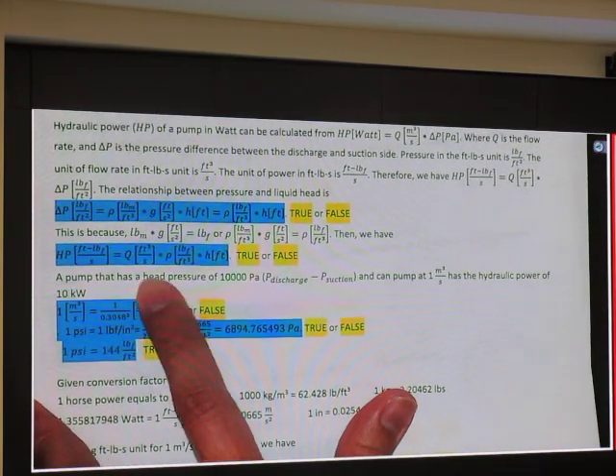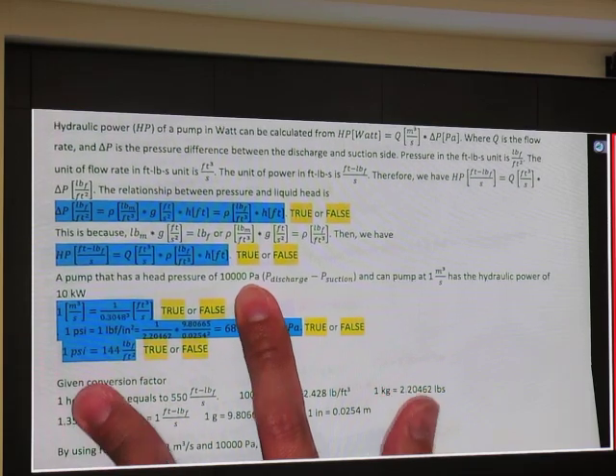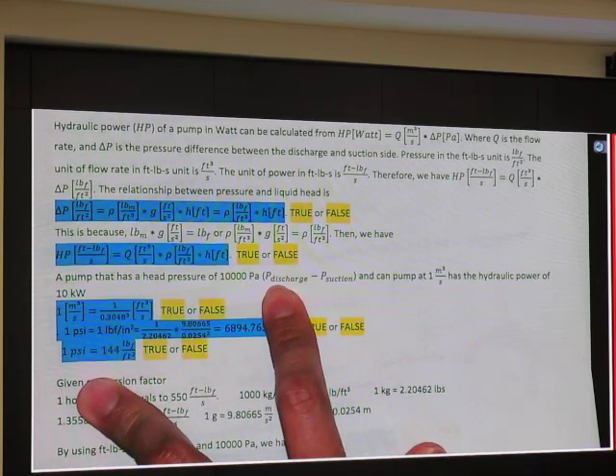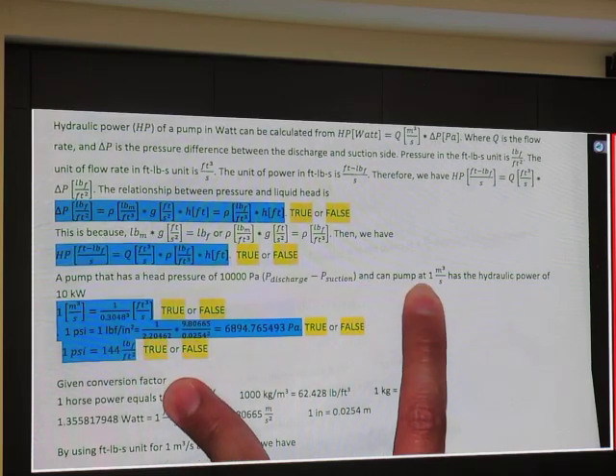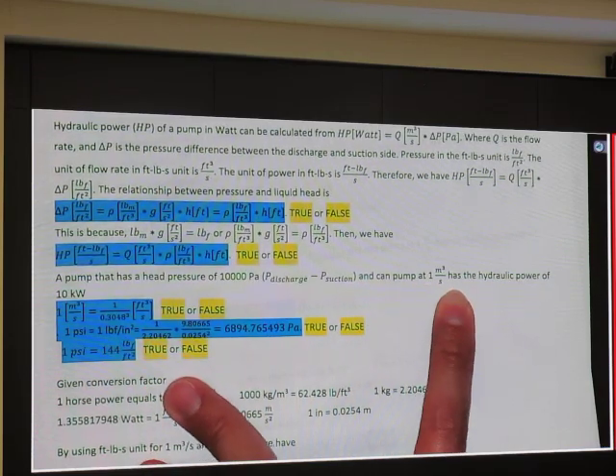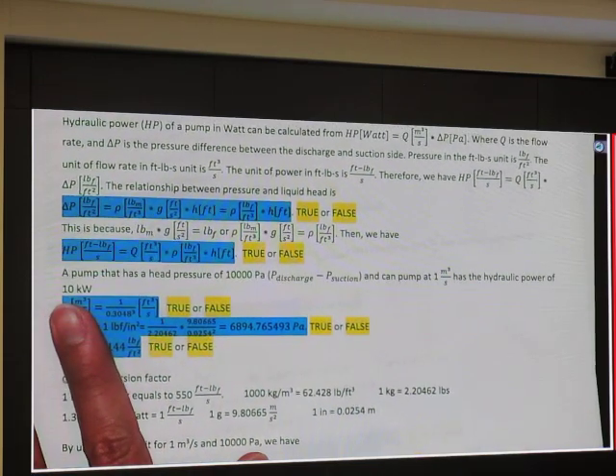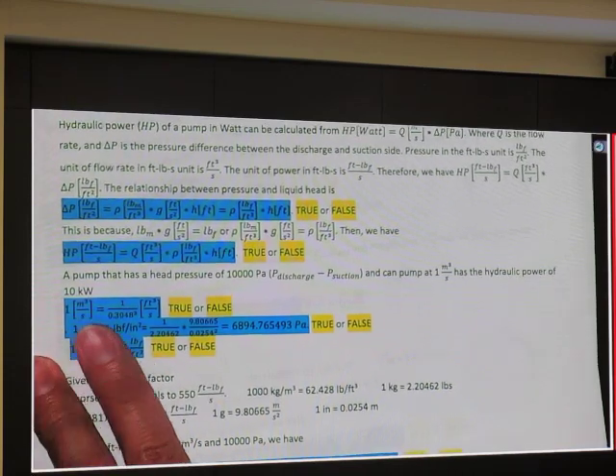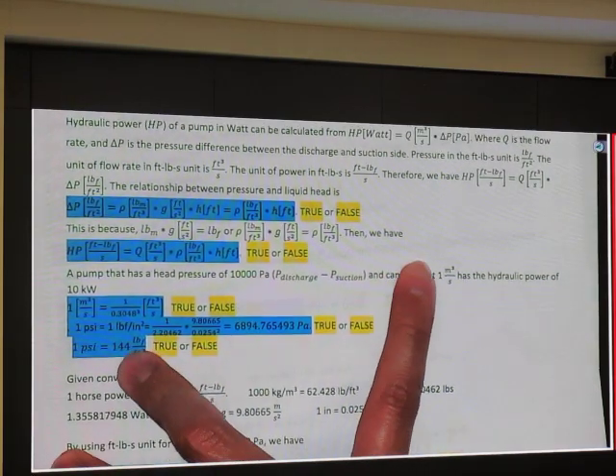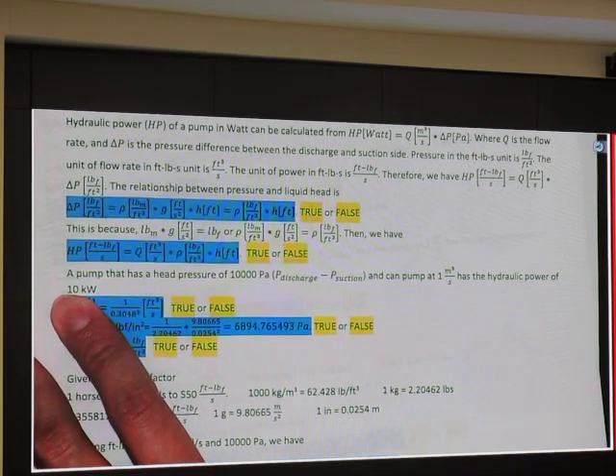A pump that has a head pressure of 10,000 Pascal, or in parentheses discharge minus suction, and can pump at one cubic meter per second has a hydraulic power of 10 kilowatts. This is not hard to prove, it is true. 10,000 multiplied by one equals 10,000. 10,000 watts is 10 kilowatts.